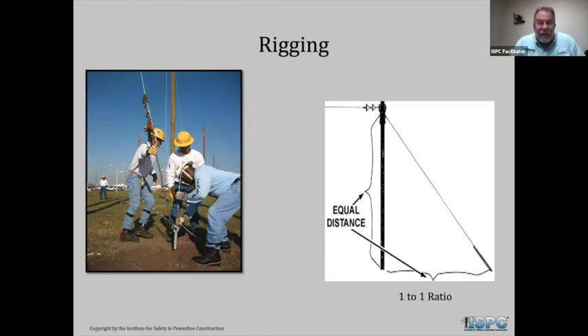If your guys are going to an existing anchor that is also backing up an energized conductor on the pole, there could possibly be some current on that guy wire that's coming down. And is it a hazard? Is it a risk to your guys? Not unless they have any differences of potential.